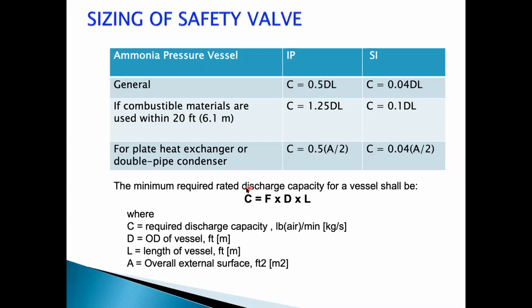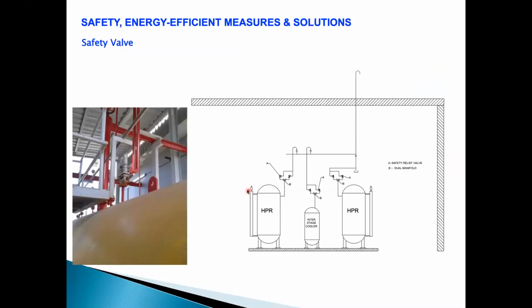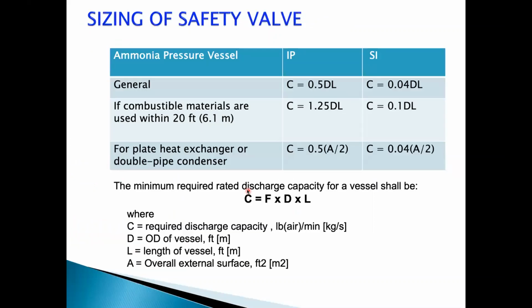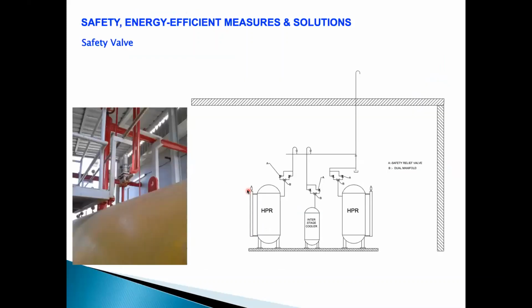Once you calculate the capacity required, the manufacturers normally give you a chart, and this is for air. When this is given for air, the manufacturers give you a chart for the safety valve at different pressures, with the air capacity. So you have to select a safety valve higher than the calculated value. Normally, when these safety valves are installed into the plant, we need to make sure that they release properly.